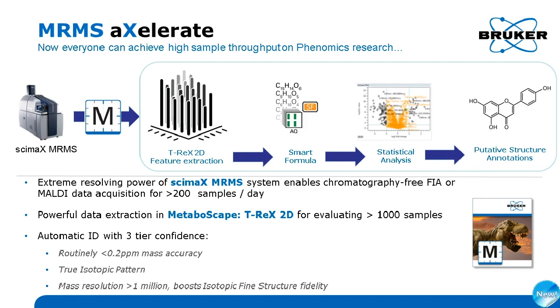I also want to present the dedicated Accelerate workflow, built on the scimaX MRMS platform. This platform provides very high sample throughput — over 200 samples per day — by skipping chromatography completely and recording just one spectrum per sample on this very high-resolution MRMS instrument. We get a resolution of more than 1 million, enabling isotopic fine structure, and a mass accuracy below 0.2 ppm. This combination of high resolution and high mass accuracy allows formula determination and profiling of large sample cohorts.